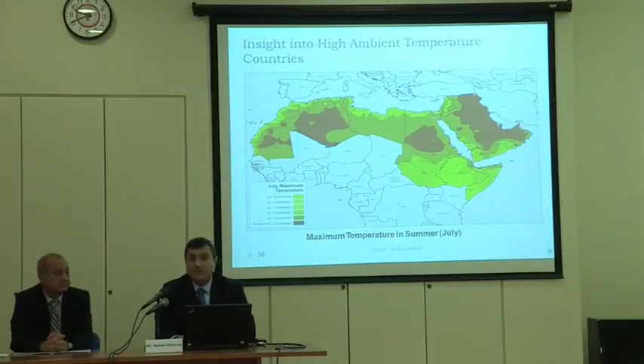More into this slide was shown by Ayman. You could see what we mean by high ambient. We're speaking about countries where the temperature could reach 50, 55 degrees C, and we'll see later that what we define as high ambient is really the design conditions, not the maximum temperature. This is a really misleading term. People think, why are you using 46, for example, even though in Kuwait the temperature may reach 55, or in Dubai it may reach 51 or whatever.